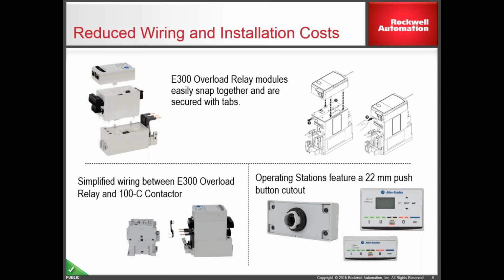With the E300, what engineering did is they designed this little control module adapter that takes the power from the E300, wires it through one of the output relays and back up to the contactor coil, assuming that the coils rotate 180 degrees on the load side. And what this does is basically eliminate all of the red wiring with the removable terminal plugs.